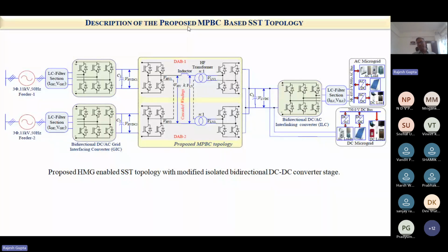I hope something inside, but it's again debatable. You can have a lot of other topologies also which can do these type of jobs. I'm not saying isolation is a must. Bidirectional DC-DC converters are commonly used in these applications, which are non-isolated, but limited to low power applications. So non-isolated is better for low power, but for medium to high power, we need isolation. Isolation in a power circuit can only be provided through a transformer, whether low frequency or, in this case, high frequency.